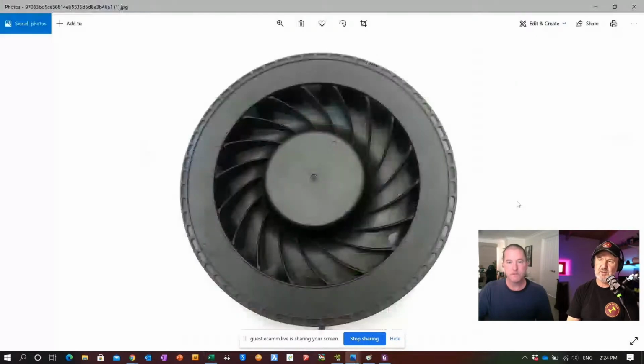Going back to your pull apart - oh, that's the fan. Yep, that's a centrifugal fan. We use a centrifugal fan rather than an axial fan because centrifugal fans can create more static pressure, which is much better for weaving air through the tortured path through the battery.